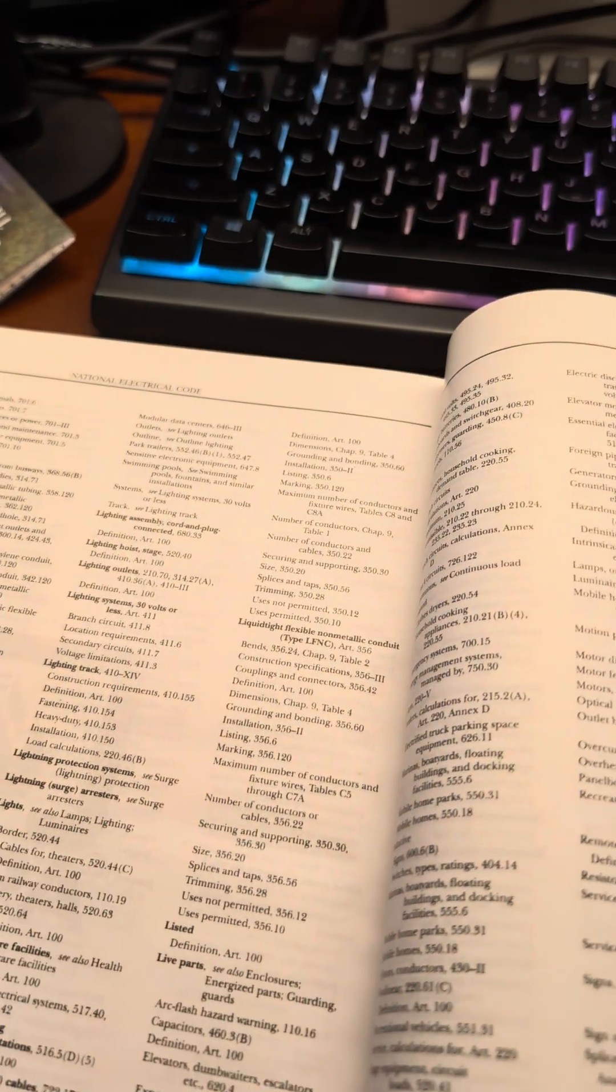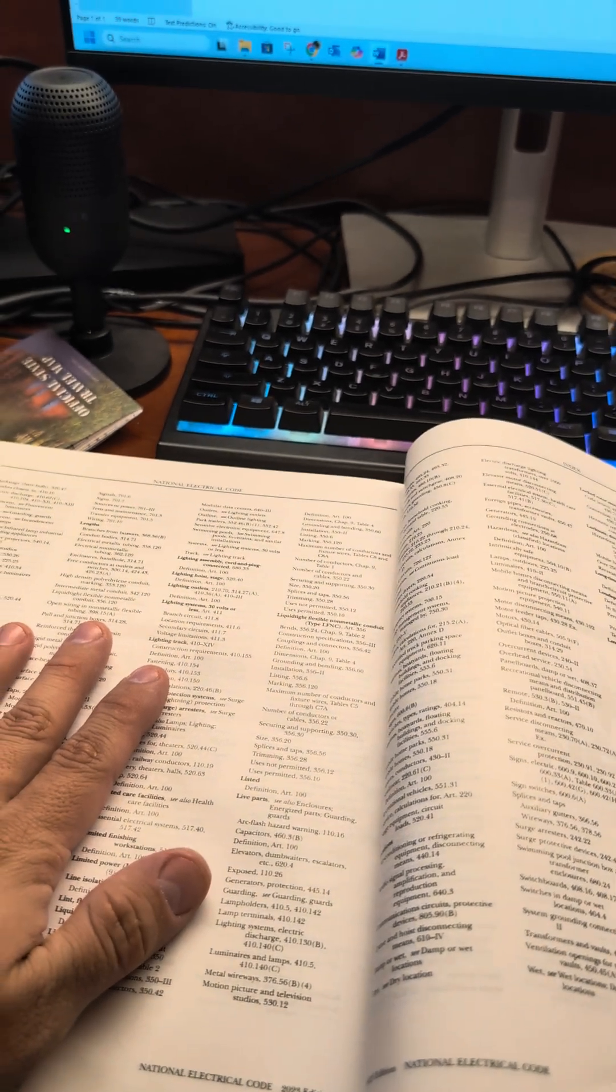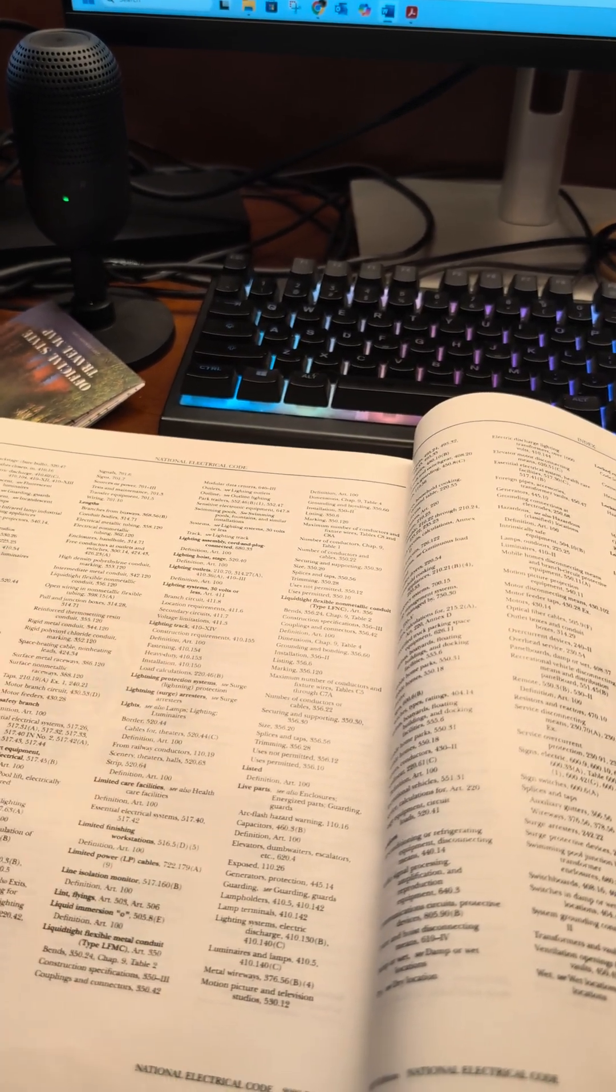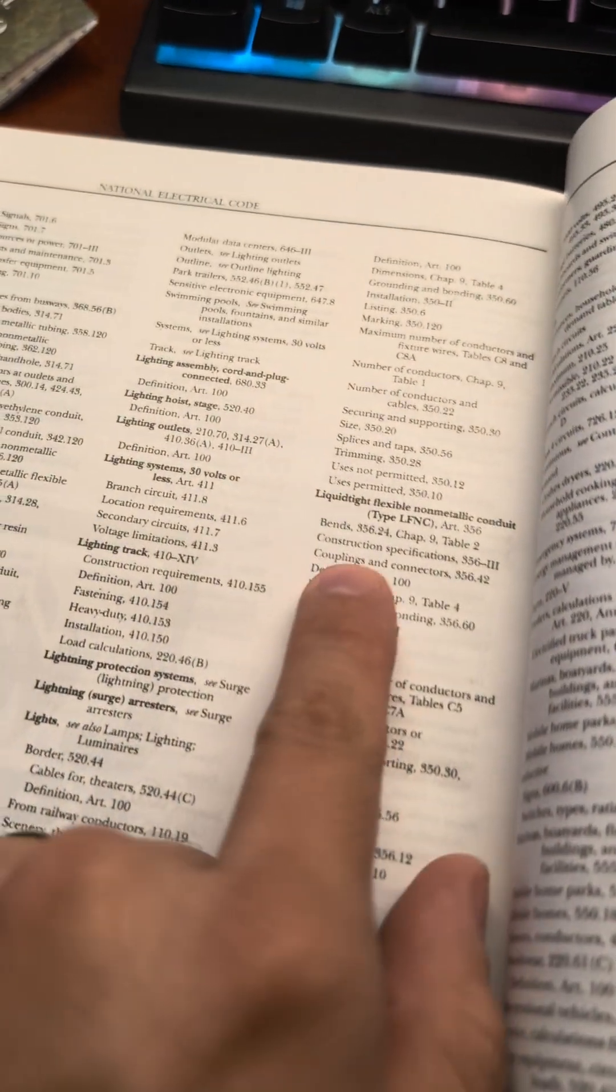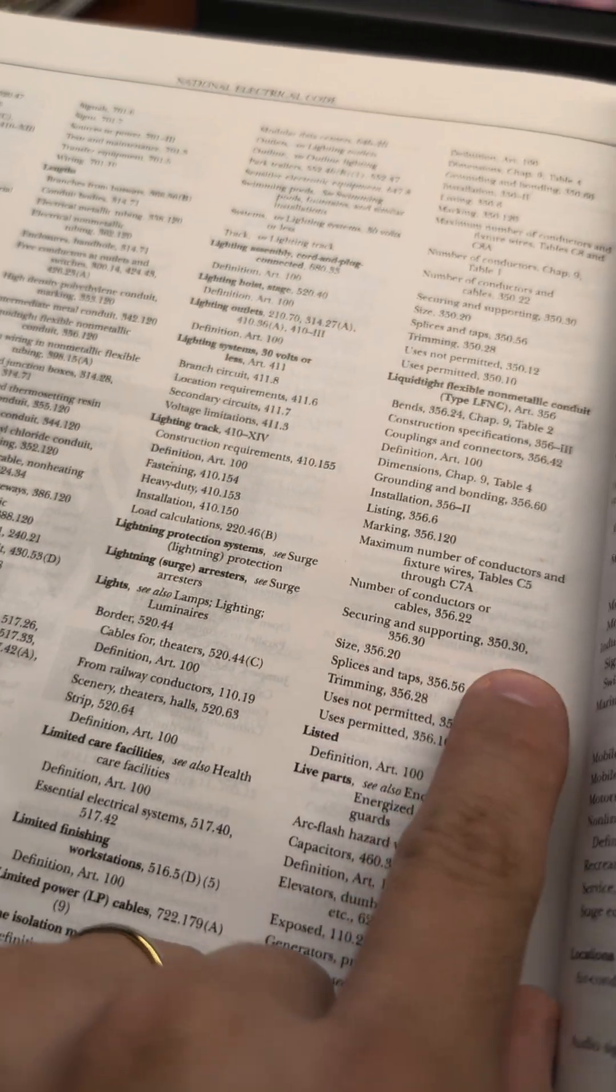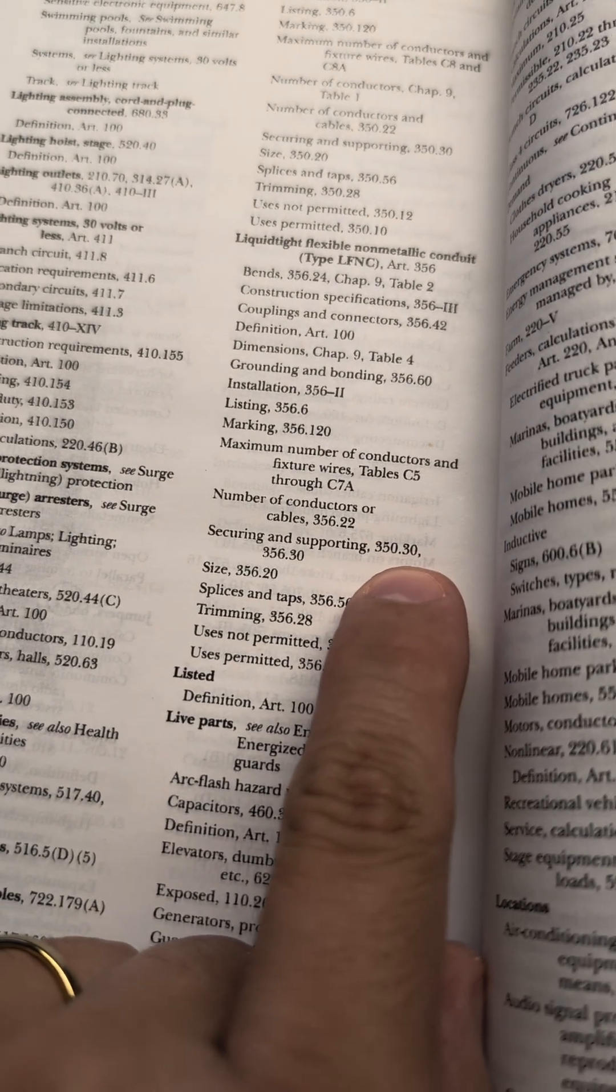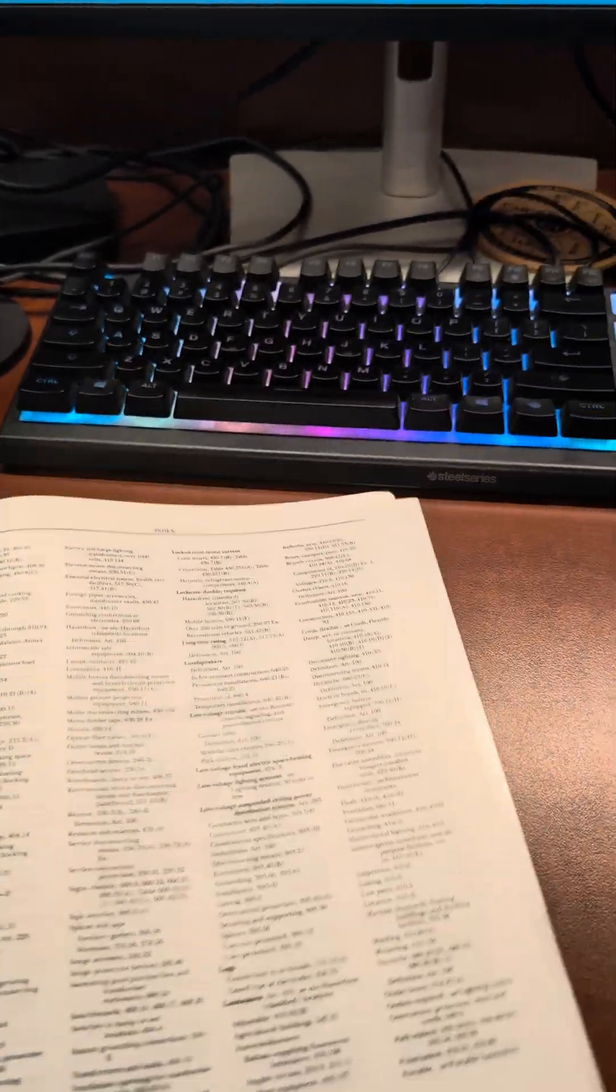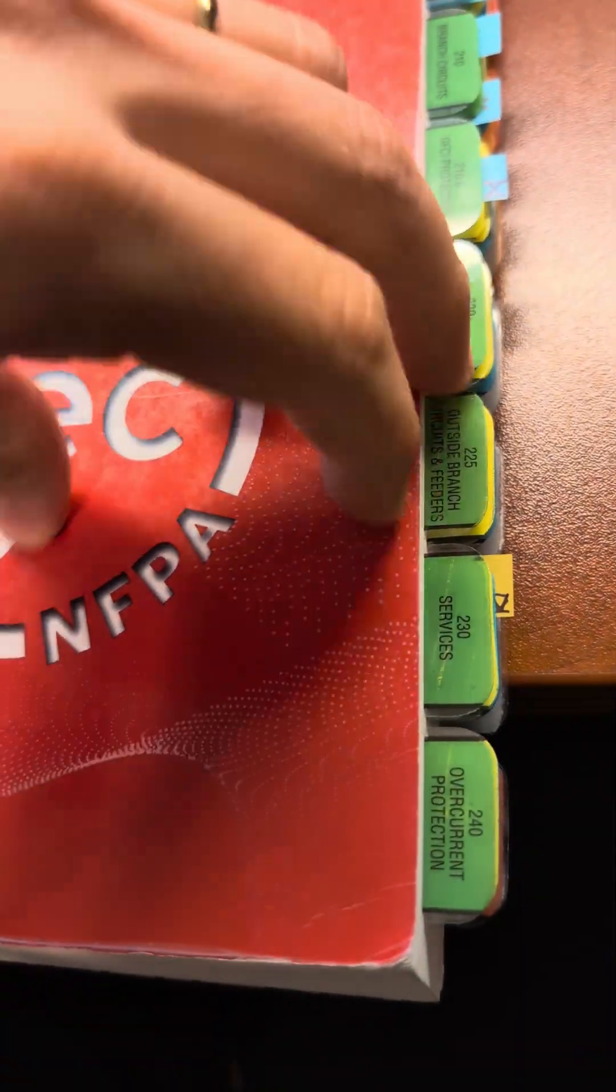I showed you a trick previously in another video talking about securement, or not securement, but just tricks about Chapter 3 in general. If I wanted to go to non-metallic and I go to securing and supporting, notice the end of it, .30 as well. So every time I want to find a securement article in Chapter 3, it's going to be .30.